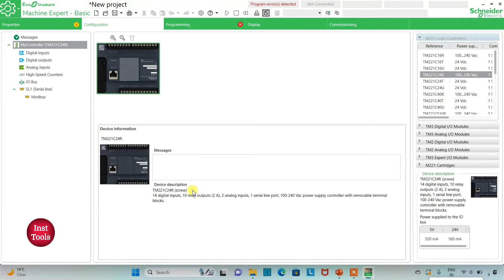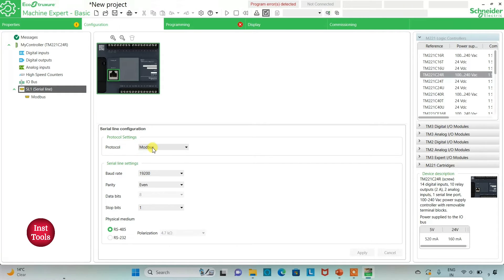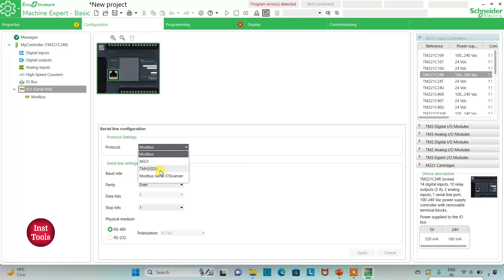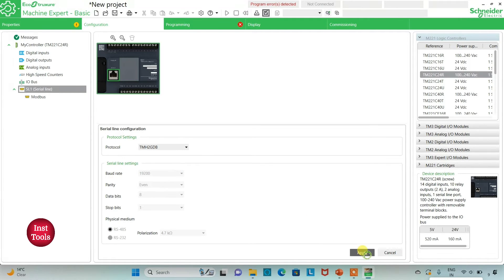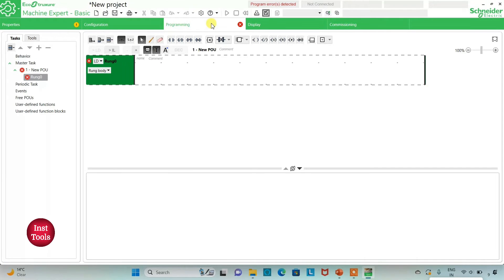Here is a device description about TM221 C24R: it has 14 digital inputs, 10 relay outputs, 2 analog inputs, 1 serial line port, and 100 to 240 volt AC power supply with removable terminal blocks. I can also go to serial line and select the protocol as TMH2GDB. I will keep it TMH2GDB and click apply, then go to the programming tab to draw the ladder diagram.